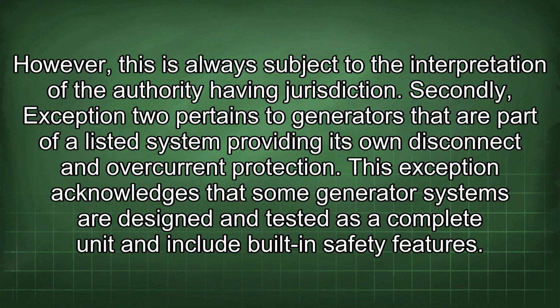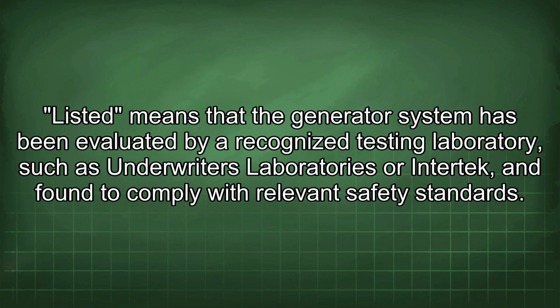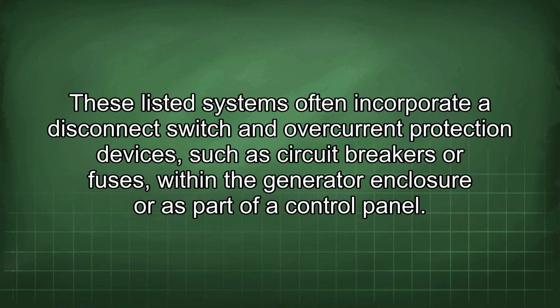Secondly, exception 2 pertains to generators that are part of a listed system providing its own disconnect and overcurrent protection. This exception acknowledges that some generator systems are designed and tested as a complete unit and include built-in safety features. Listed means that the generator system has been evaluated by a recognized testing laboratory, such as Underwriters Laboratories or Intertek, and found to comply with relevant safety standards. These listed systems often incorporate a disconnect switch and overcurrent protection devices such as circuit breakers or fuses within the generator enclosure or as part of a control panel.